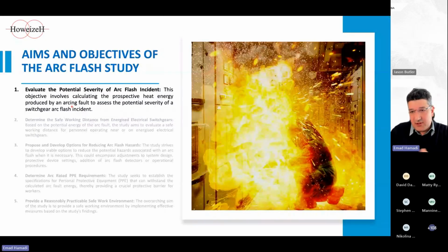Now let's focus on the main subject of the presentation and talk about the aims and objectives of an arc flash study. Why would we need an arc flash study and what does it give us? In my experience in the design field in the UK, I've seen that the arc flash study, unfortunately, was often considered a fancy piece of information or a good-to-have at best. However, this perspective, I think, has changed in recent years, which is good news. The arc flash study is essential for several key reasons, which guide us in mitigating arc flash risk in general. Here I'm trying to mention five main reasons.